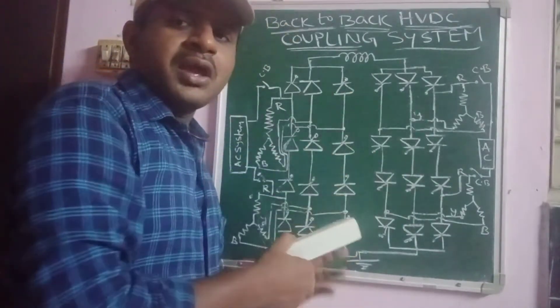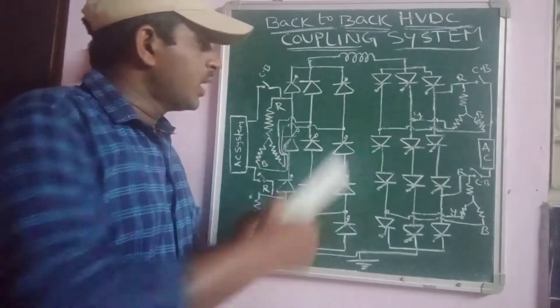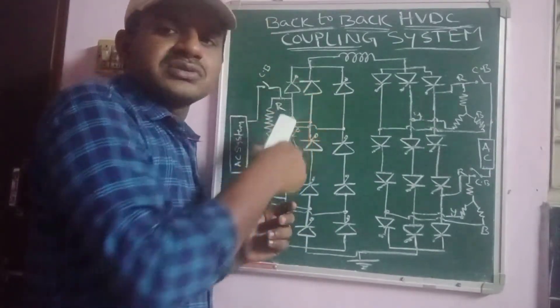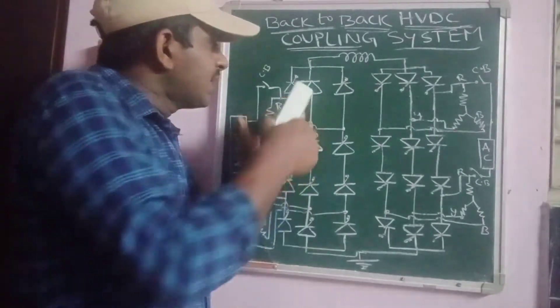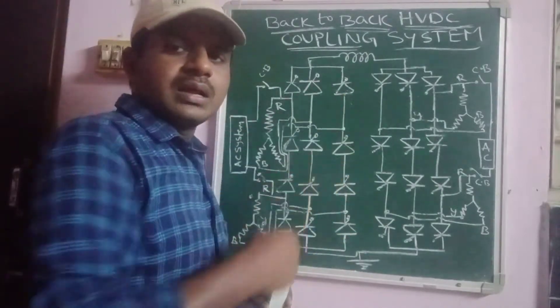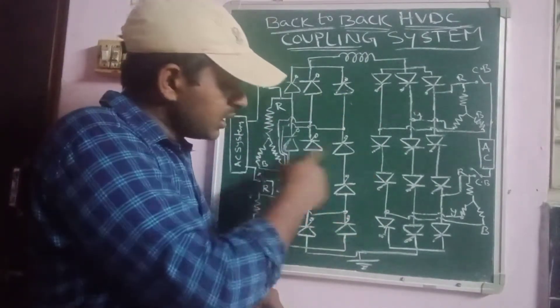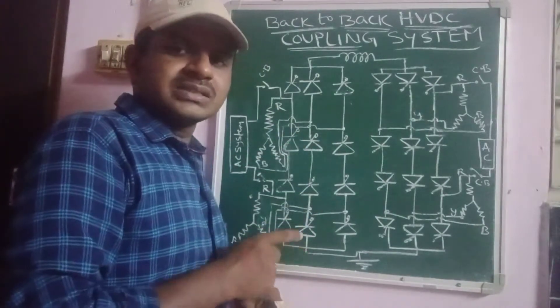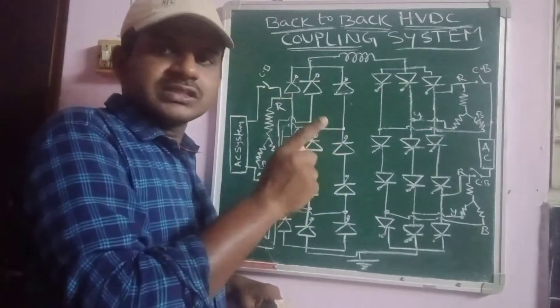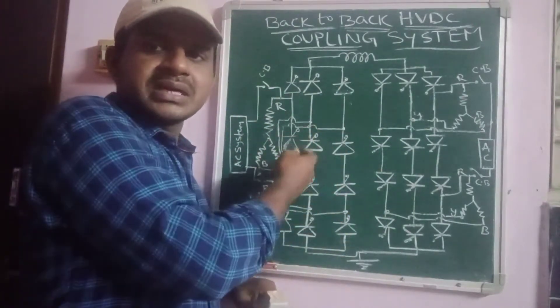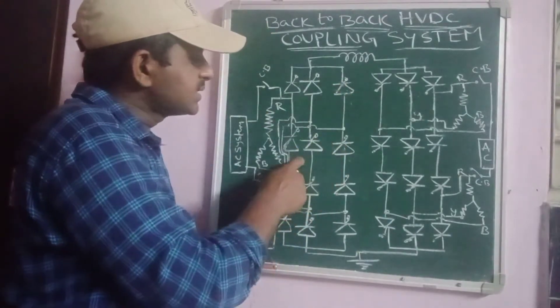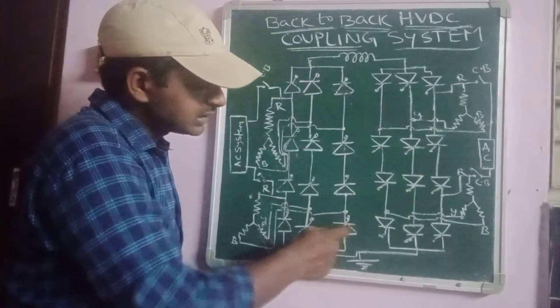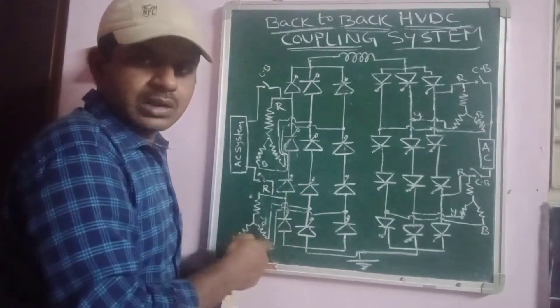Looking at this diagram, this is the rectifier station. As discussed in the previous session, according to the connection of thyristor valves, we can identify it as a rectifier station. The total converter station may contain 12 thyristors, and these 12 thyristors generate 12 pulses — each thyristor generates one pulse. Six thyristors are connected to one three-phase transformer, and another six thyristors are connected to another three-phase transformer.